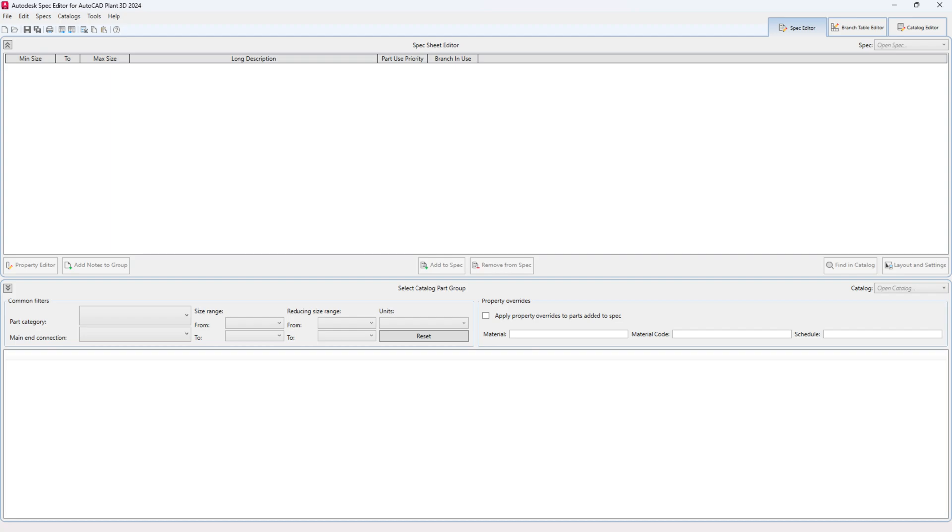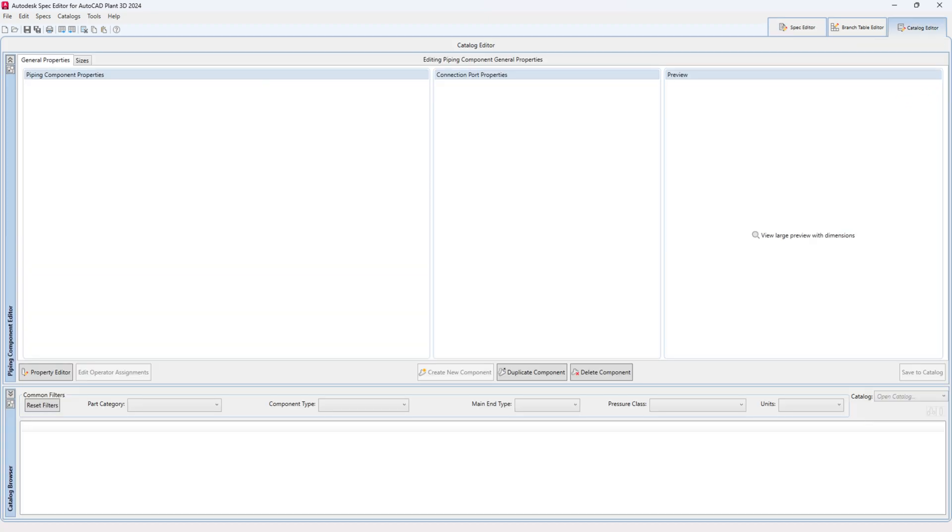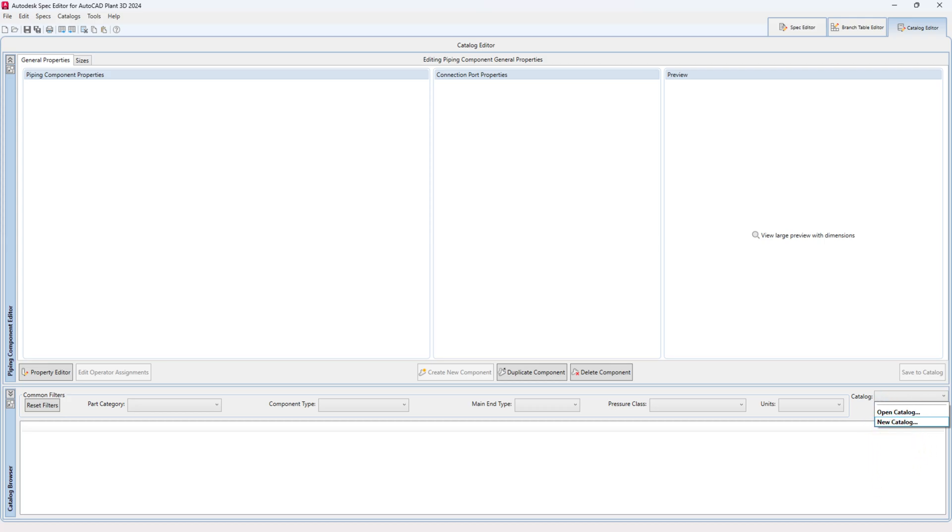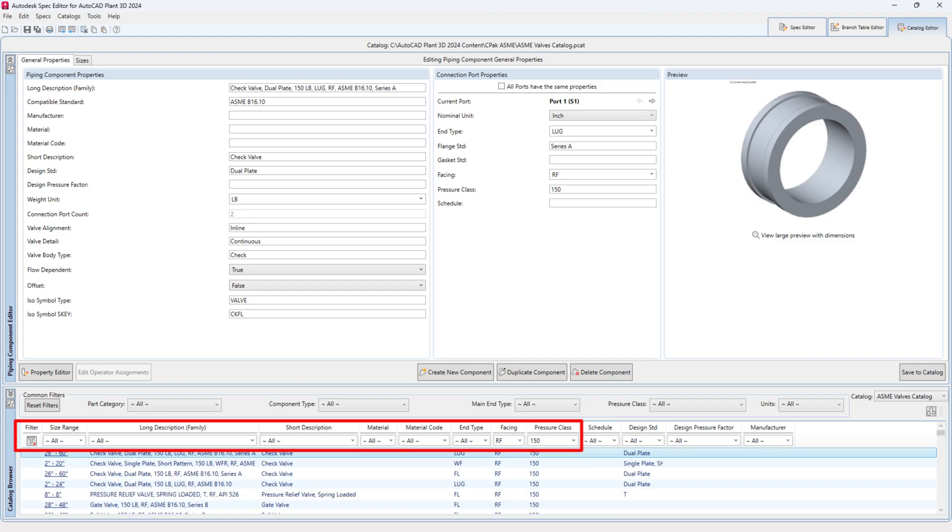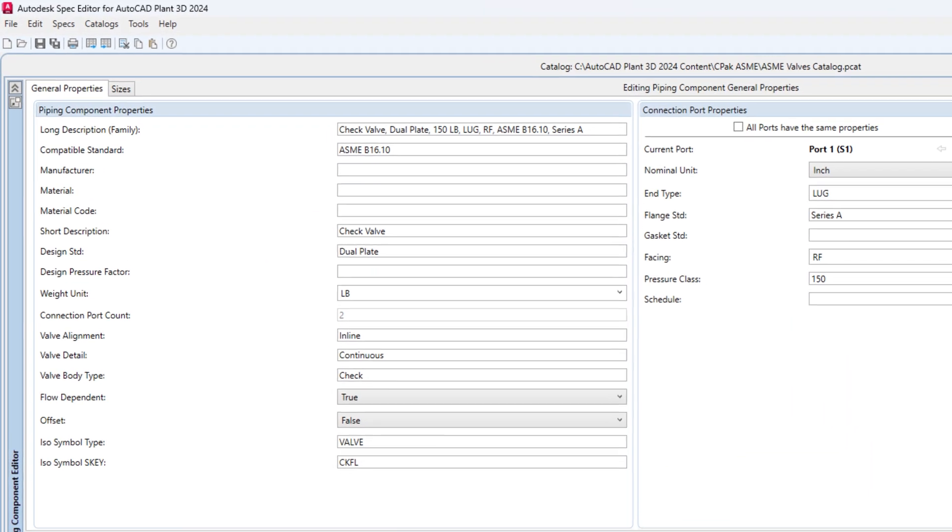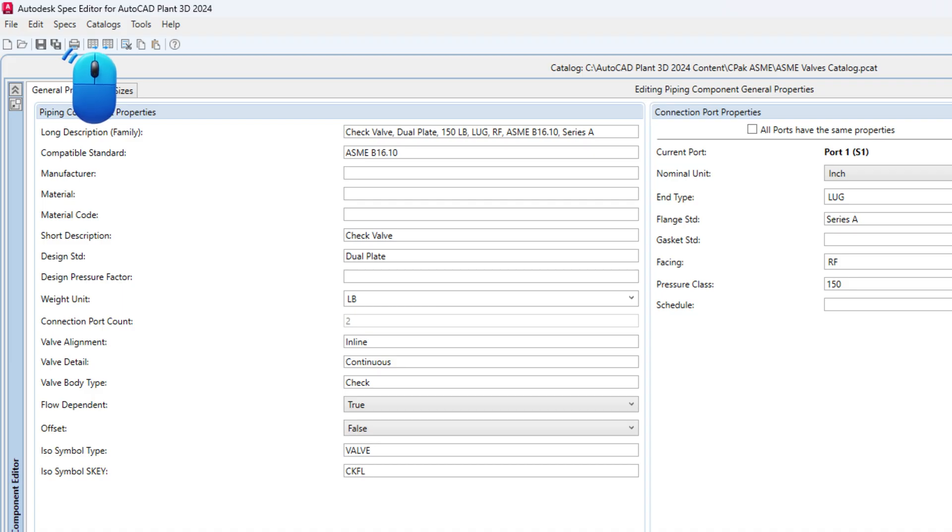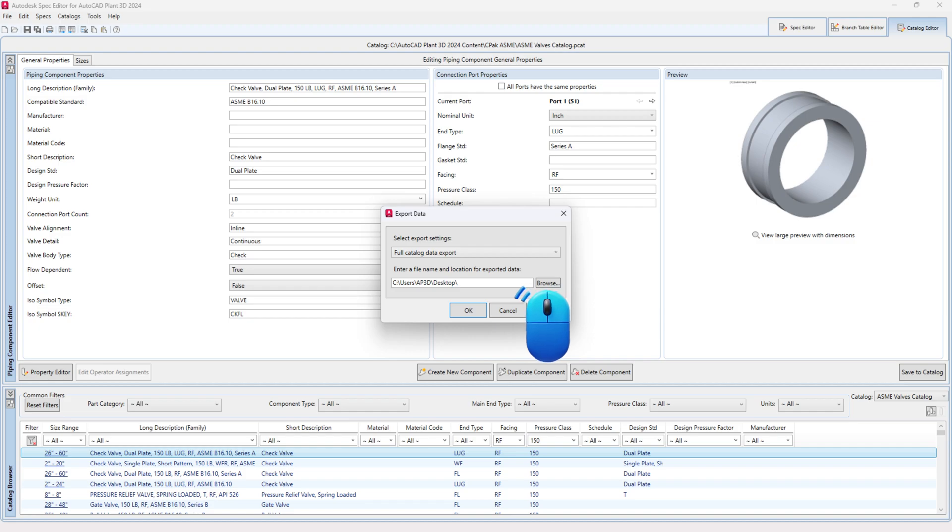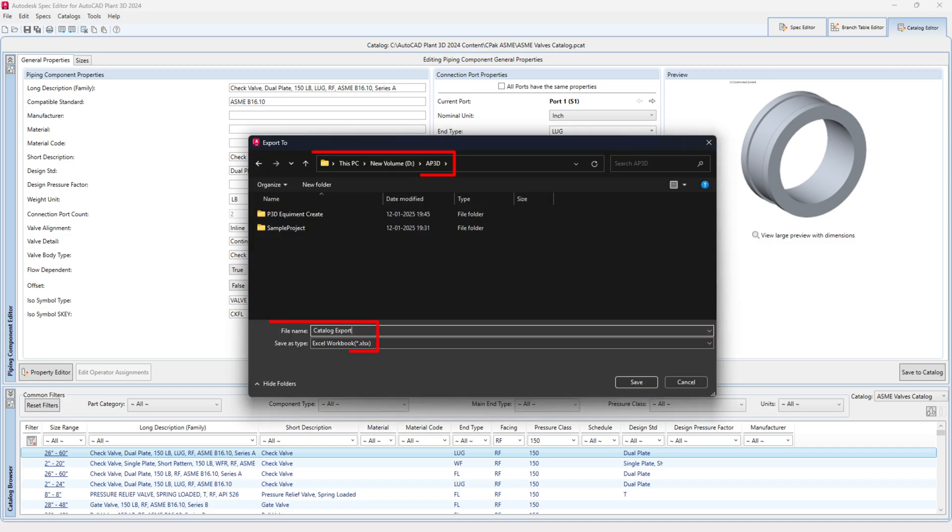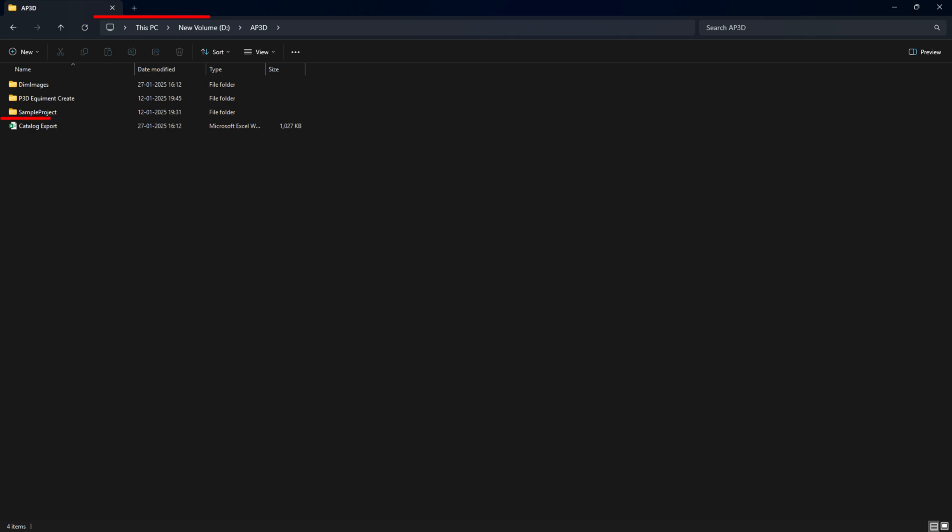First, open the spec editor for Plant 3D. Switch to the Catalog Editor tab. Choose the catalog from the drop-down that has the component you need. You can filter the components or do a full catalog data export. Click the Export to Excel button. Select Current Catalog Filter Export or Full Catalog Data Export from the drop-down. Choose where to save the file and name it. Click the Save button and then OK.